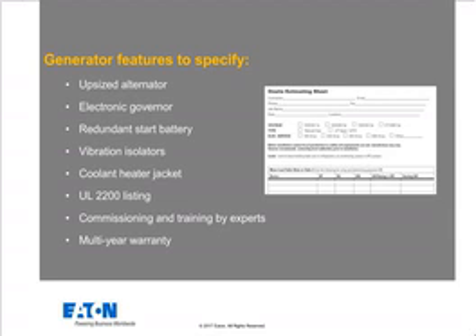So if I'm a data center operator, for example, and I want to know what features are important in the generator, the kinds of things that you should consider, I'll just list a few of them here. One of them is an upsized alternator, going to be a little more able to handle the kinds of distortion that the generator would see with a UPS load. The next item shows an electronic governor, but keep in mind, we have seen applications where a mechanical governor worked better than an electronic and vice versa. So we recommend discussing this with the generator vendor to see what their recommendations are before you make a decision.